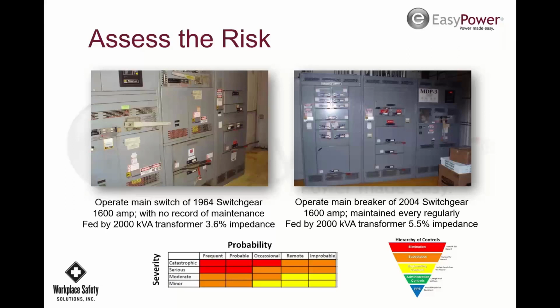However, if I go to a place where an arc flash hazard analysis has not been done, then I have to go through and use tables. And if you use tables, if it's over 8 calories, you have to wear a full suit. So I would have to bring a full suit. If I'm doing data collection for a new client, I have to go in there with a full suit because you can only layer up if an engineering study's been done. So I hope that helps.